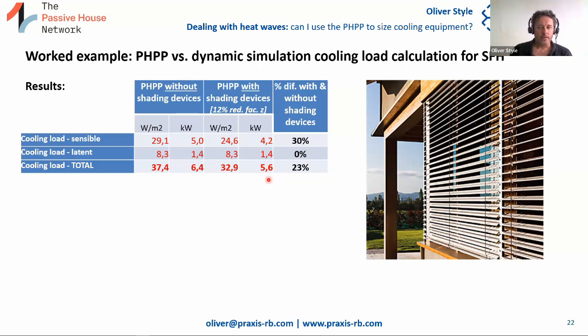The difference in costs between a heat pump of, let's say, 7 kilowatts and 5 kilowatts, at least here in Spain, is about 200 euros. It's just irrelevant, really, the difference in that power when you get that low. So my advice would be, don't put 5 kilowatts in, put 7 kilowatts in, and assume that people don't drop the blinds, because the capital cost of the system is not going to increase significantly in any way at all. The operating cost, the energy bill, is not going to increase significantly at all, because between a 7 kilowatt and a 5 kilowatt heat pump, it's going to be able to modulate down to about 30% of its nominal power. In which case, that means that the machine will be able to drop its power down when there's not a huge cooling load, and the energy bill is not going to be significantly higher.